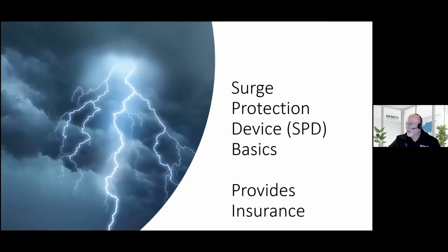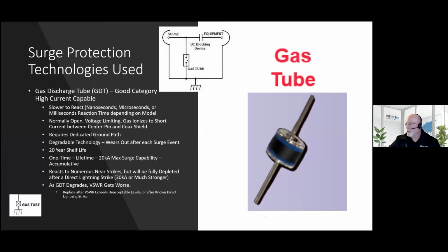So surge protectors, we use different technologies in the products themselves. Here's a gas tube, very basic, and the good, better, best. It's a good product. It's depicted here schematically like that. It's a normally open device. It's a voltage limiting device as well, so it's going to react to a sudden rise time in voltage, at which time the gas inside here ionizes, creating a momentary short. The surge then comes off of it.